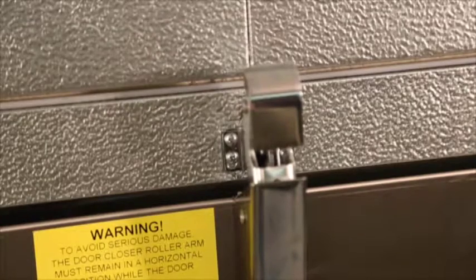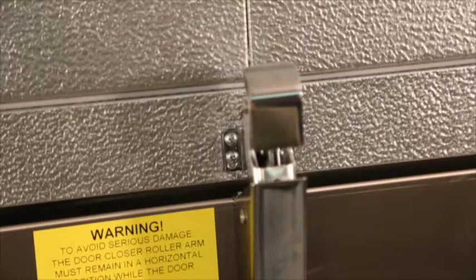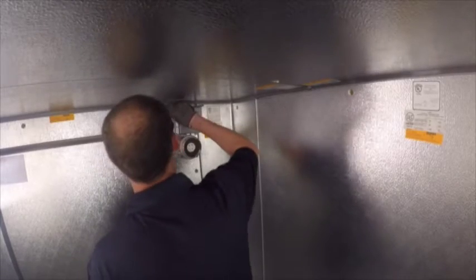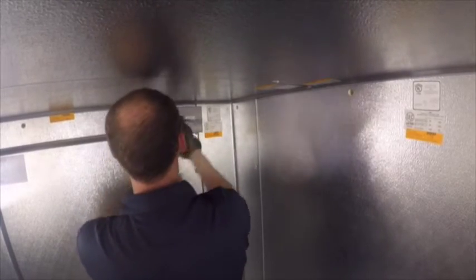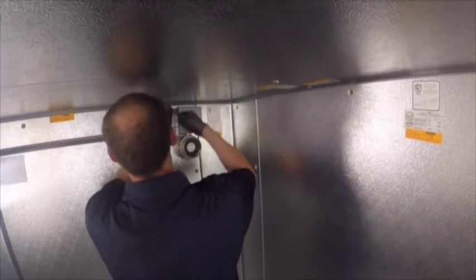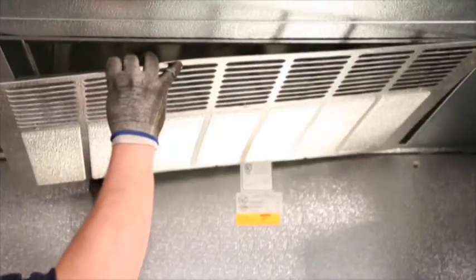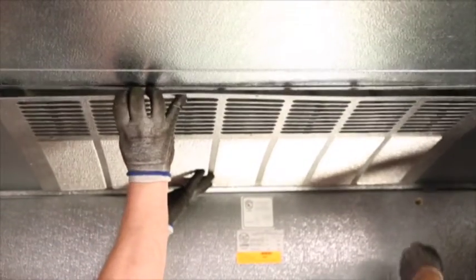Once all the wall and door panels are erected and locked securely together, ceiling panels are rechecked for position. Now all ceiling panels will be locked securely to the wall panels. That'll ensure a tight and proper seal for optimum refrigeration and energy efficiency. Once the ceiling-mounted refrigeration is in place, secure the interior latches and seal the cowl to the ceiling at the gasket seam above the diffuser panel using the silicone provided. Replace the diffuser panel in the correct orientation.